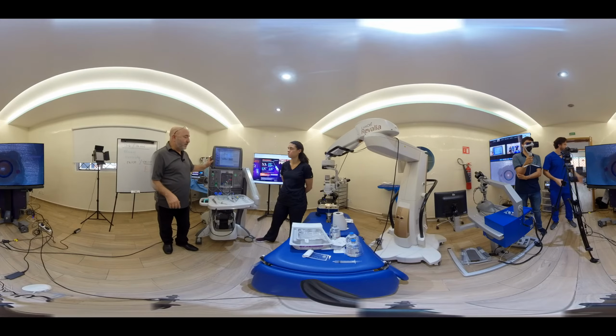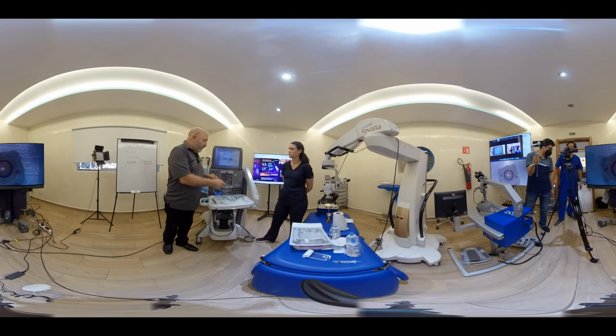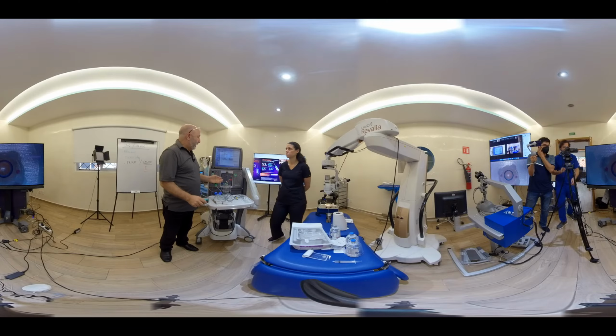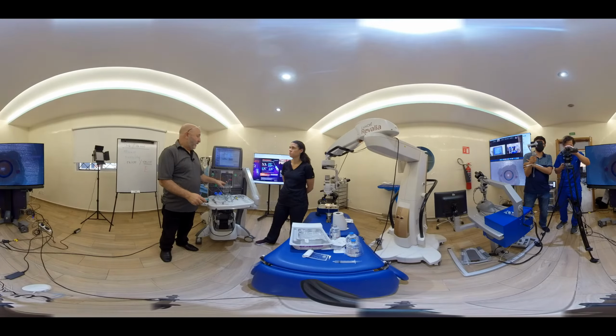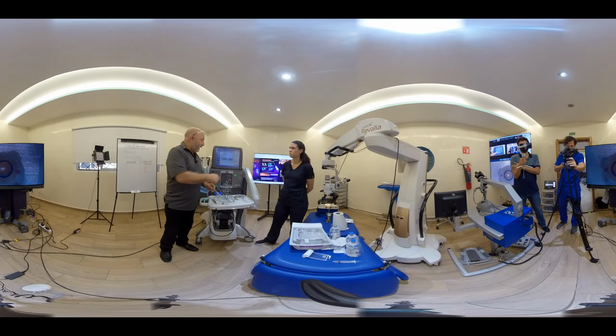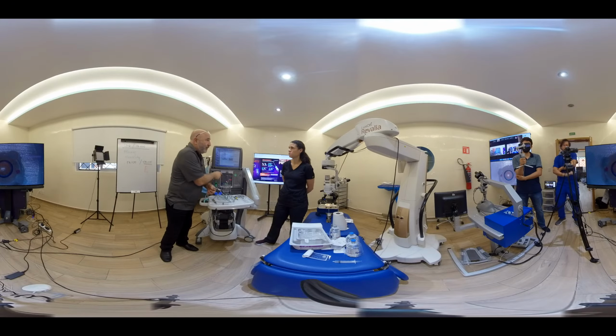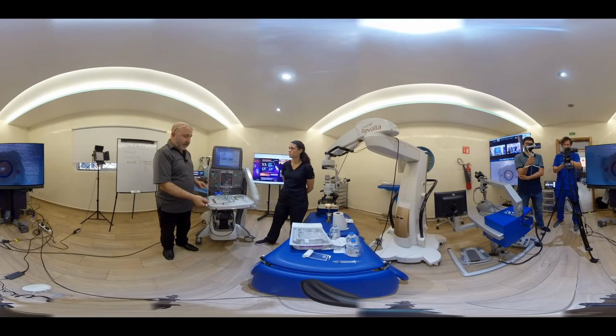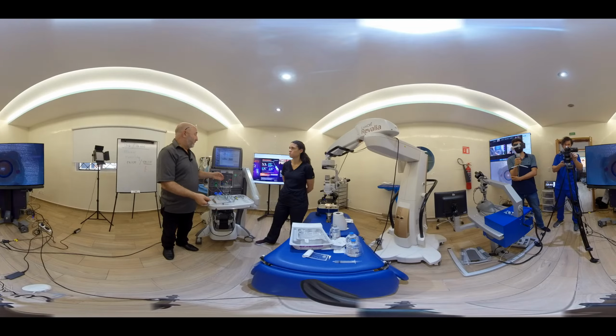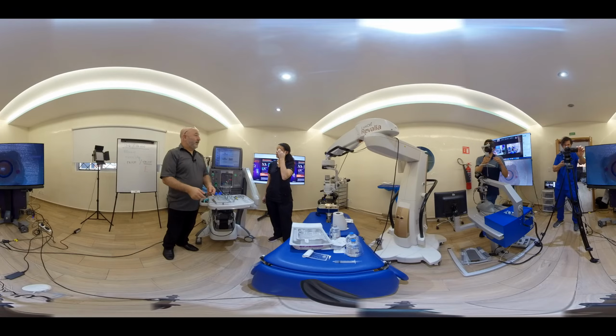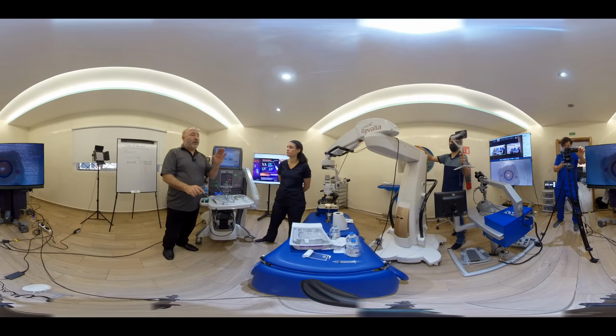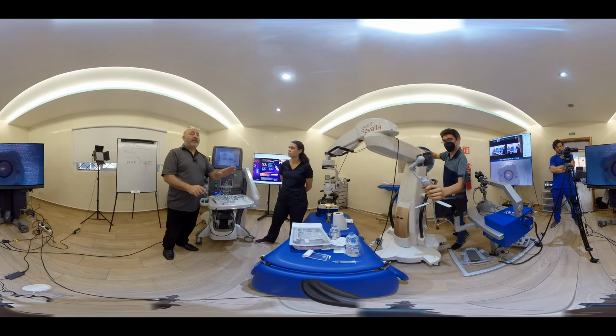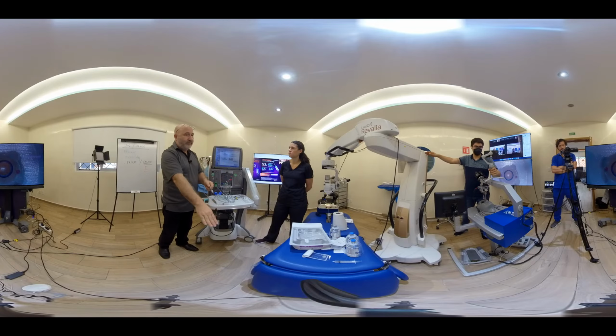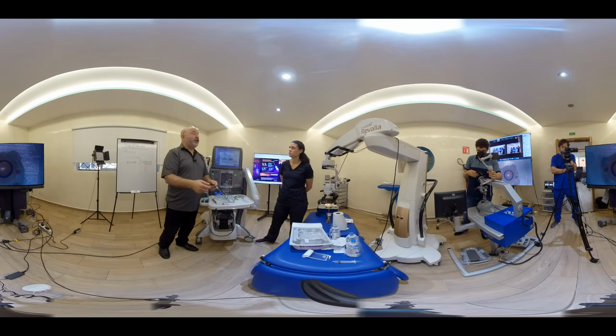The other effect is on suction. Because when I press the pedal and I'm 10 inches below and I've got 20 millimeters of mercury gravity effect here, when I first touch the pedal, it unlocks one of those pincher valves. So it opens the aspiration line to the aspiration chamber. What do you think happens? All this aspirant starts flowing back into the eye because it's got 20 millimeters of mercury pushing it out. But if I set the patient eye level, when you're at zero vacuum, it recalibrates the zero to be 20 millimeters of mercury. So it's applying a vacuum so that way there's no downward force of fluid going back into the eye. So you don't get regurgitation.